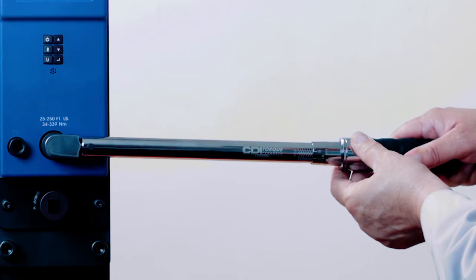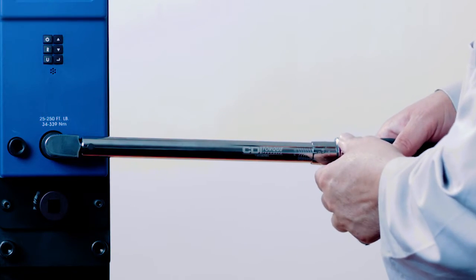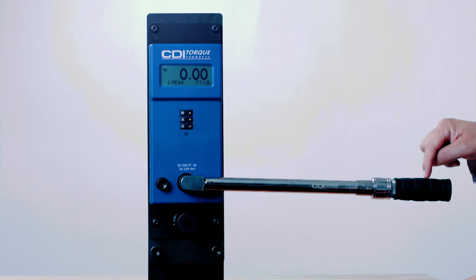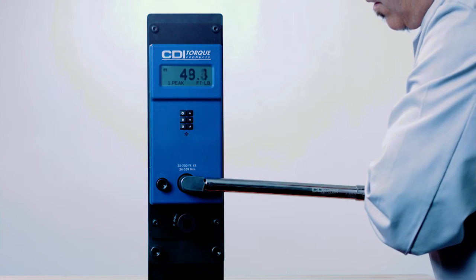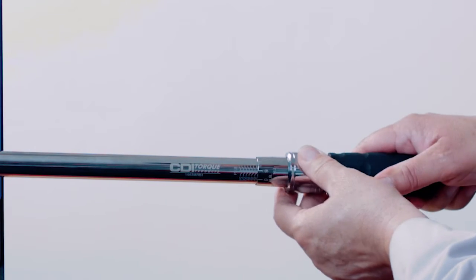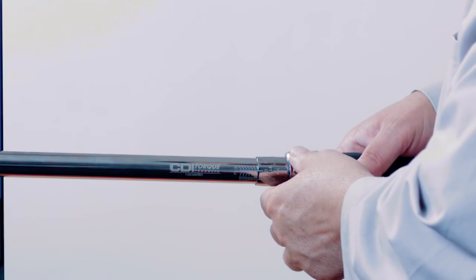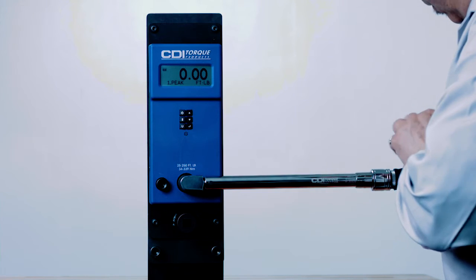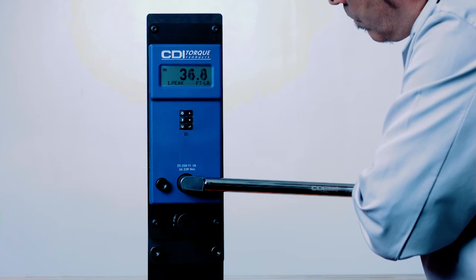Now set your torque wrench to your desired setting. Engage the wrench square drive completely in the DTC socket. Always apply force at the center of the torque wrench handle. For this demonstration, we'll set the torque wrench to 50 foot-pounds of torque. Apply force at the center of the torque wrench handle. Stop applying force when the wrench clicks.